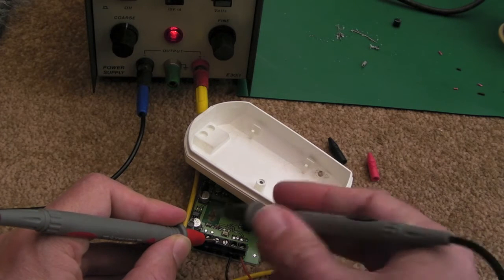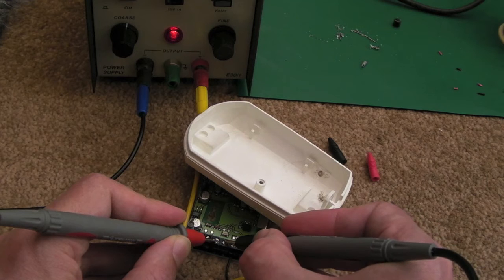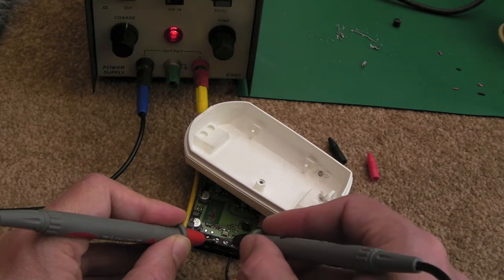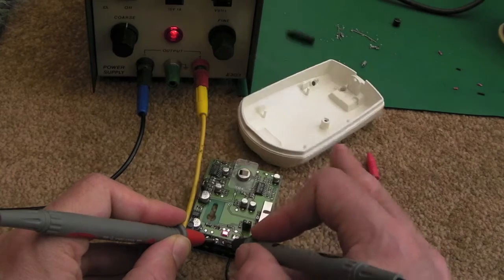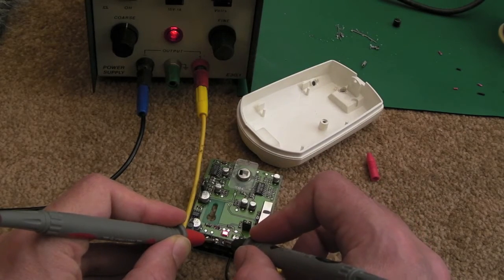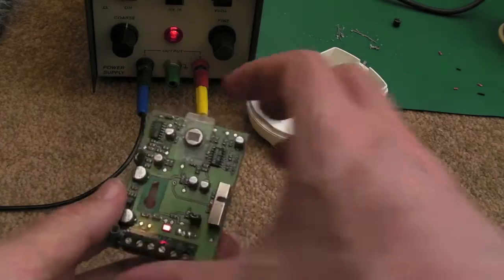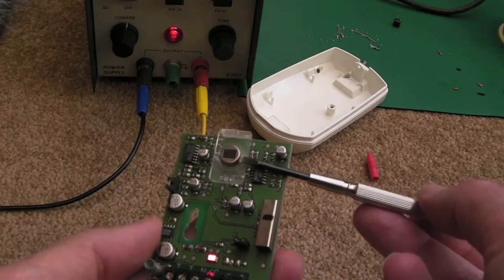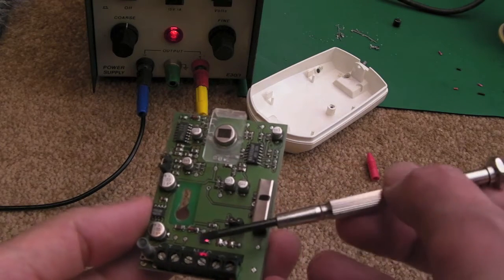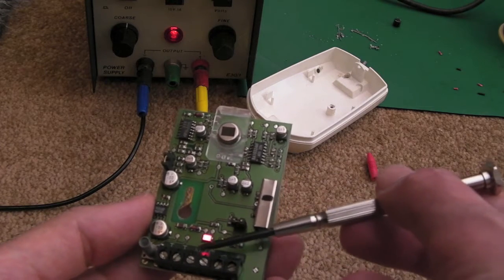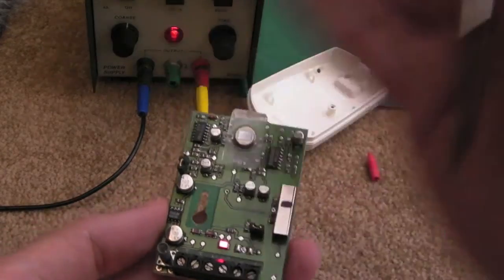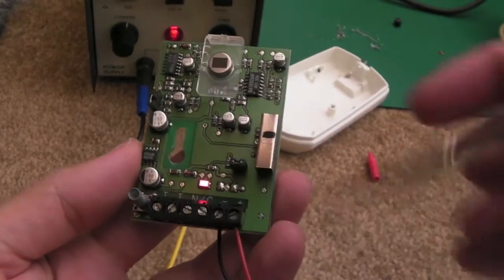I'll put it on resistance, see if I can measure the actual resistance. Yeah, 22 ohms. So I put it back on sounder. So I move that across, get a bit light, it goes off because open circuit. So that's the way it works. When this is not detecting anything in the room, a person, a heat signature, or movement, it will be closed, like 22 ohms. And obviously it goes open circuit there when something goes in front of it and the red light comes on to indicate.